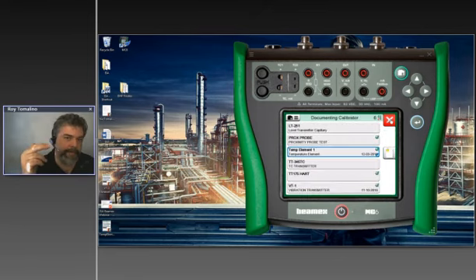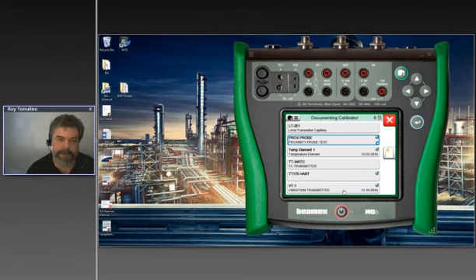And before I show you the calibration certificate, I want to show you something. At the most recent ISA Process and Safety Control Symposium, we did some calibrations of something else, and you can see that on the calibrator here. We calibrated a proximity probe, and we also calibrated a vibration transmitter. We always want new input from you on what you want to see next in the next video set. What are those things that you're calibrating that you need a little extra help with, or something that needs to be demystified? If it's this, let us know. We can do more info on vibration or proximity testing.